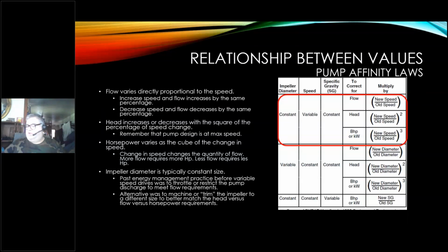In the old days, and John may remember this, past energy management practice before variable speed drives was to throttle or restrict the pump discharge to meet the flow requirements. We would actually cut down the valve. We actually have balancing valves now to dial in the flow to the right head pressure, or the resistance to flow, to get the right water flow. However, the problem is that the speed stayed the same. And if I had to cut that pump down a lot, you'll be riding the pump curve to the left and it starts resisting flow. So why would you do that?